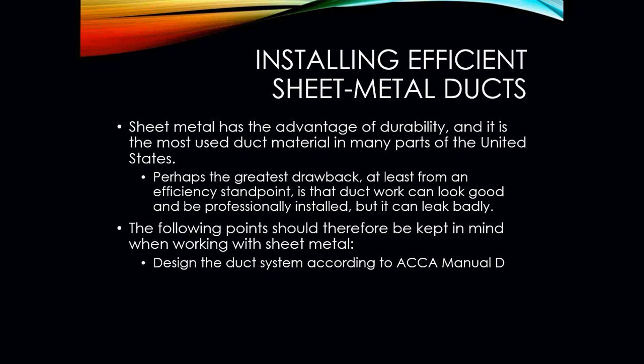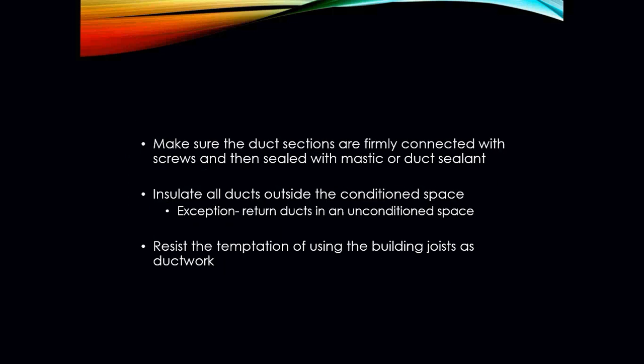You're going to want to design your duct systems according to the ACCA Manual D. Nowadays, there are many duct sizing programs that you can purchase and put onto your laptop or computer that will do all of the calculations for you to figure out how many CFMs go to each room, how big your ductwork needs to be, and your takeoffs and all of that stuff. But all of our ductwork that is properly installed, and I'm saying that again, properly installed, will be installed in accordance with ACCA standards.